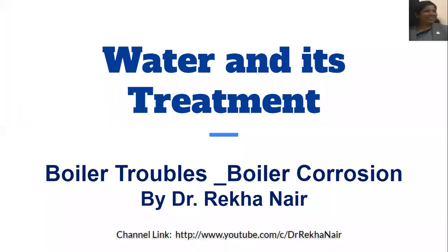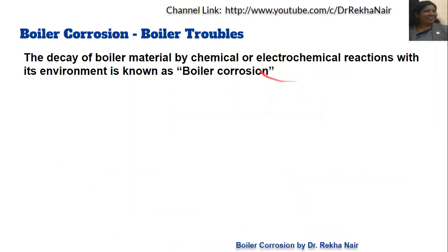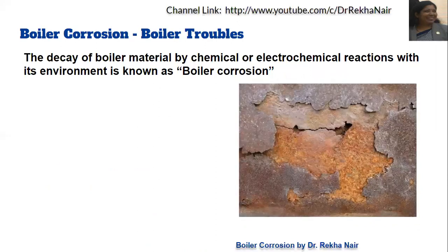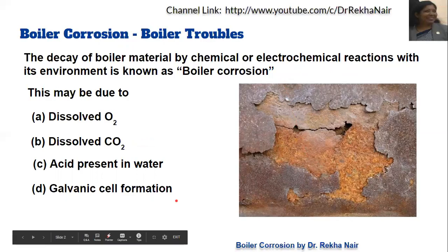Hello friends, today we will be discussing about another boiler trouble: boiler corrosion. In the previous video, we had discussed about sludges and scale, which was also a boiler trouble. The decay of boiler material by chemical or electrochemical reactions with its environment is known as boiler corrosion. You can see the effect of boiler corrosion here. This may be due to dissolved oxygen, dissolved carbon dioxide, acid present in the water, or galvanic cell formation — four different reasons for boiler corrosion.